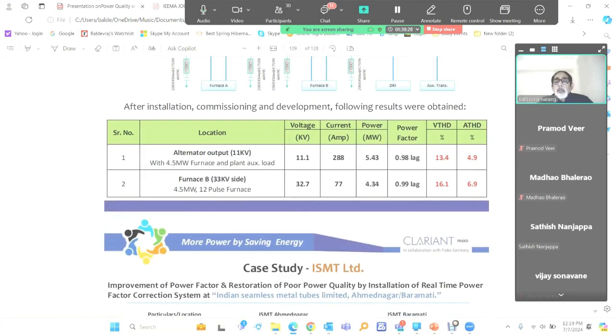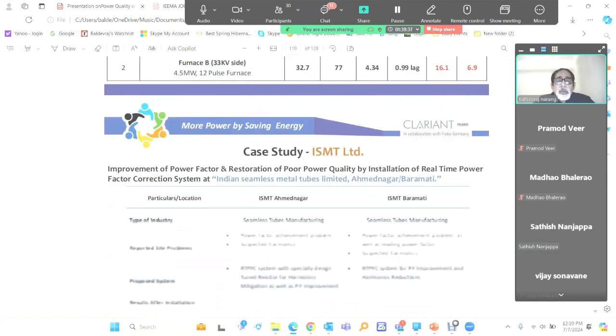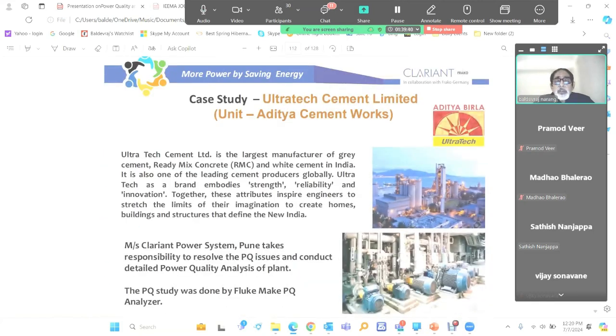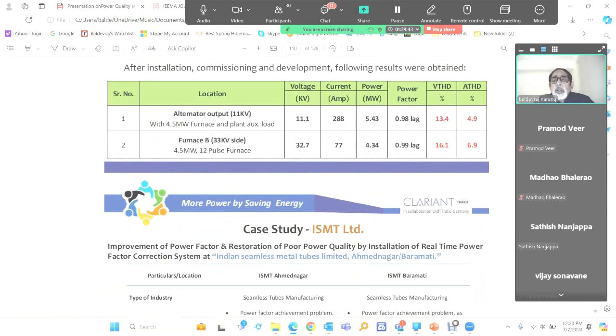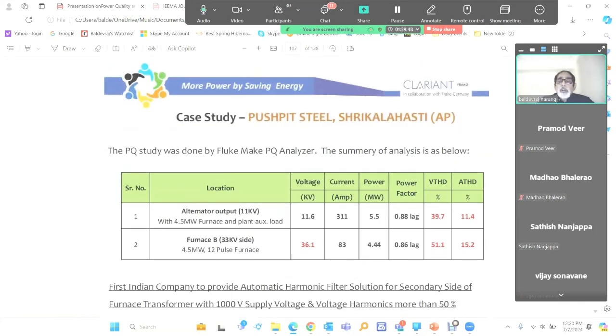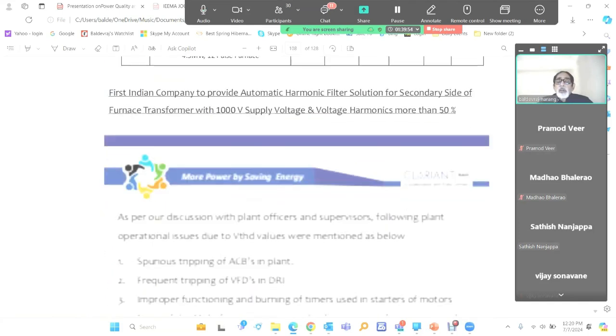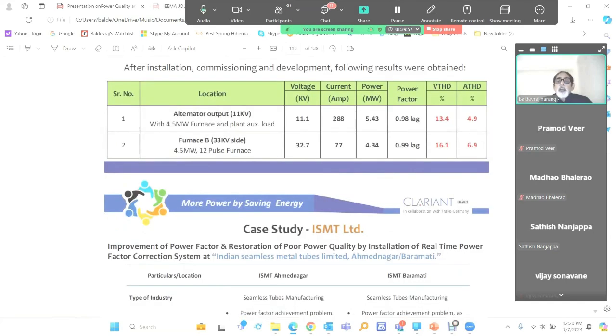They had voltage harmonics very high, and this was the alternator output. One slide is missing, I think. 39% voltage harmonic was there, and current harmonic was 11%. After giving the solution, we could reduce it, and it was within workable limits, because for an independent island system, this is also a very good value, since it is a very high impedance system. So harmonics are higher, voltage harmonics. In the grid, it is only 2% or 3%.